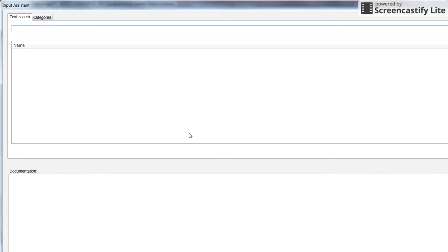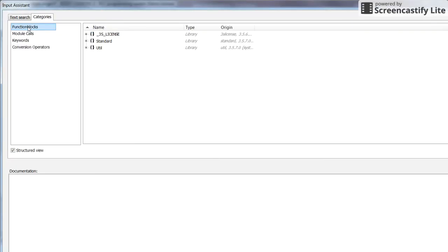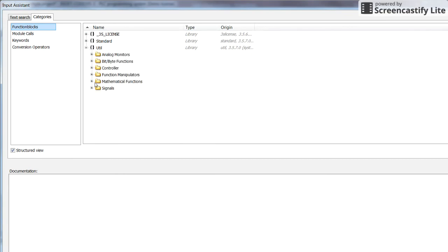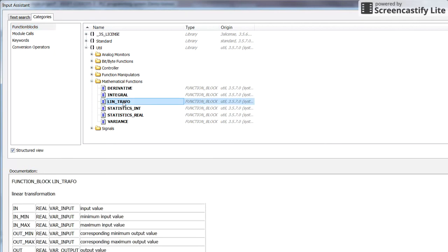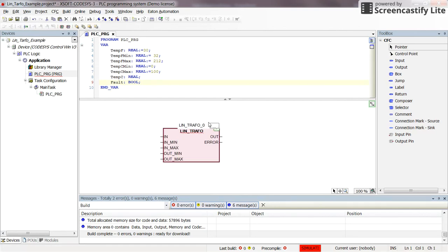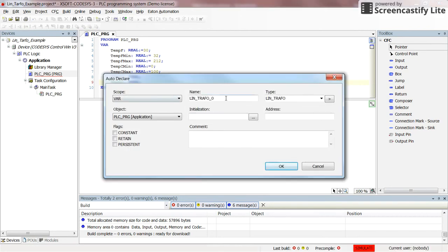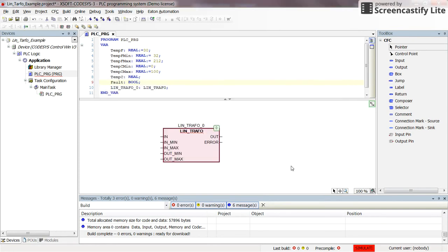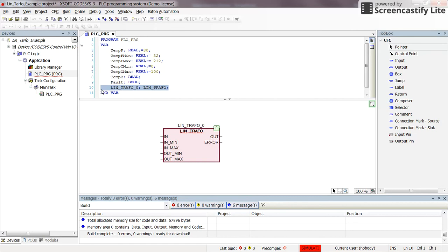Now, clicking again to determine the type of the function block, we will see Util appearing in the list of libraries, and within it we have mathematical functions and the linear transformation. Double-clicking on it and pressing Enter, we need to determine a name for the instance of this function block. I will keep the default and press Enter. We need to declare it using auto-declare — the type of this new variable is linear transformation. Clicking OK, it appears in the variable declaration area.